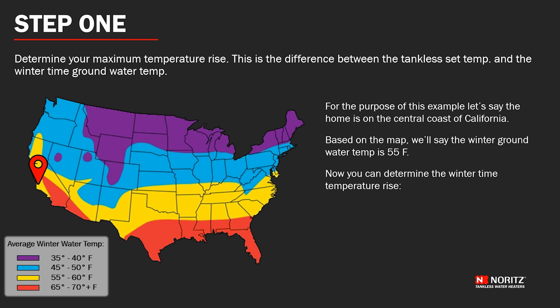Now you can determine the wintertime temperature rise. We'll assume a 120 degree set temperature, as that's hot but not scalding. Subtract the 55 degree groundwater temperature and you get 65. This is your temperature rise.